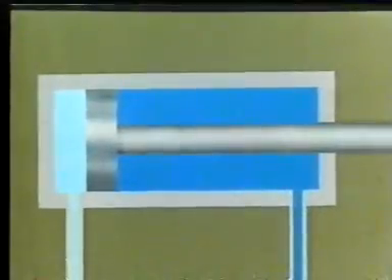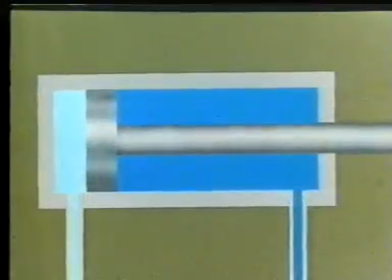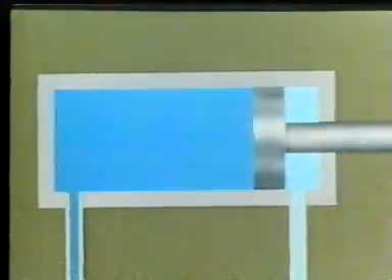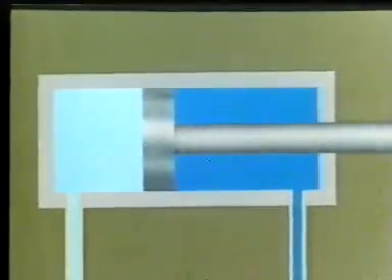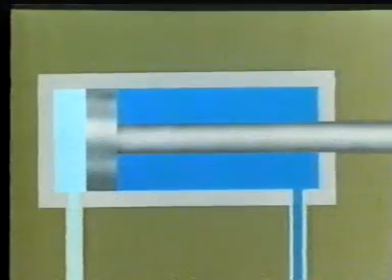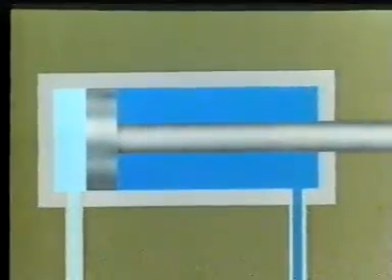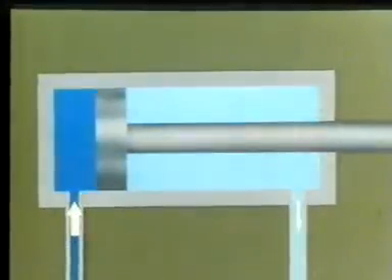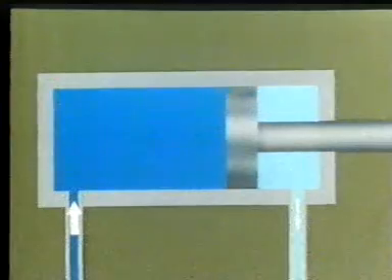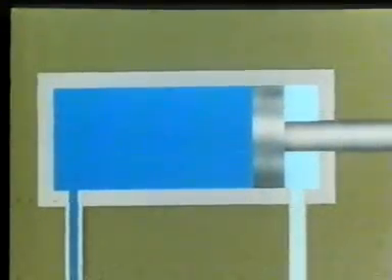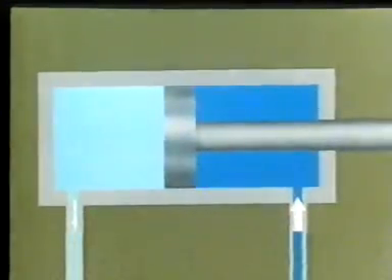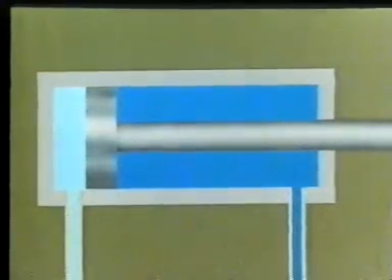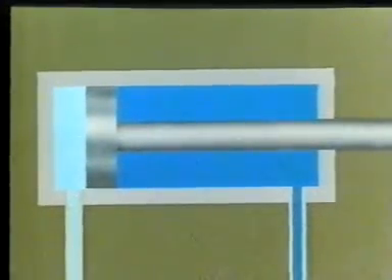The double acting cylinder can perform work on both the advance and the return strokes. If compressed air is applied to the double acting cylinder and the opposite side is exhausted, the piston rod moves out. If air is supplied to the rod end and exhausted from the piston end, the piston returns to its initial position.